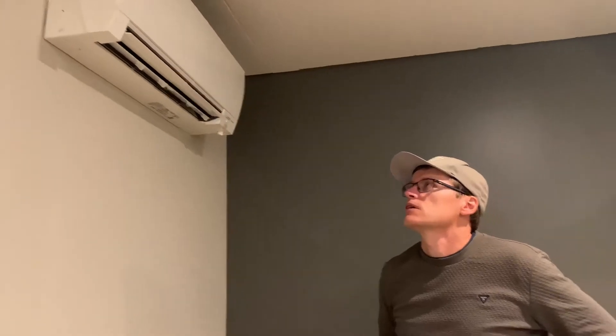Because our house is built to the passive house standard, it's a 2,400 square foot house with an almost finished basement, so there's almost 3,500 square feet of heated space. Having just three point-source systems works fine because we have the ERV system distributing air continuously around the house. So even though the heat is only getting dumped at three spots, the fresh air exhausts from the ERV are distributing the heat throughout the rest of the house. And because it's an efficient airtight house, we don't have a lot of cold spots to worry about.